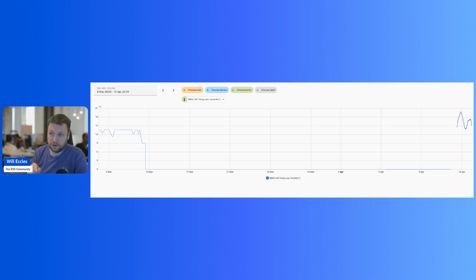In the Fox Cloud application, installers have access under settings to see battery temperature. I could see that M1 cell and M2 cell were reading -20, while the rest had temperatures in the 15 to 16 Celsius range. So I was confident the battery module at the top of the stack was registering itself as M1 and M2 cell temperatures, and that its temperature sensor had failed. Between it reading -20 and the others reading 15, and the BMS having its own temperature sensor, I'd breached some kind of temperature delta rule within the BMS firmware, causing the batteries to enter that suspended state.